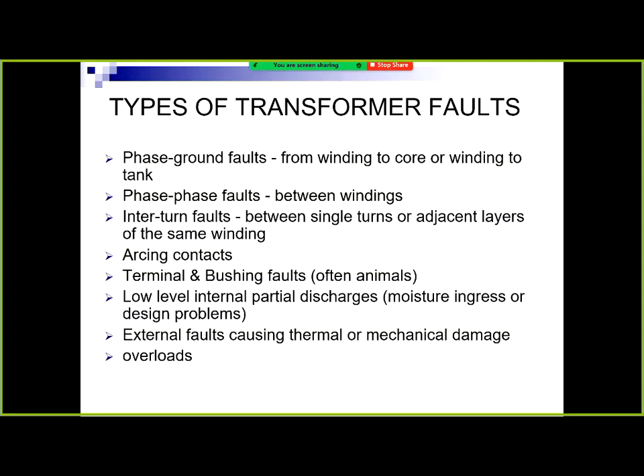Wherever we can have an N-2, so that means 2 planned items out of service, and overload a transformer, we put overload protection on there, a thermal protection. So they have a 10-minute rating and we trip them off in about 8 minutes. It just gives the operators a couple of minutes maybe to do something and drop some load off.